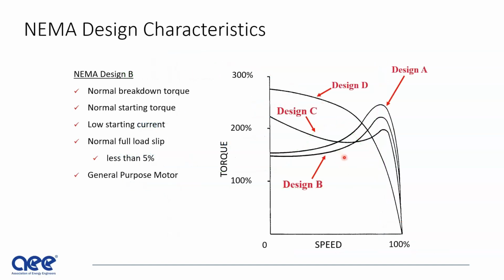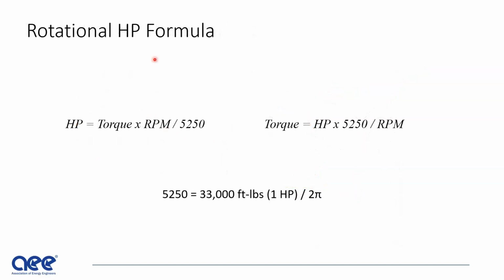Here you see the NEMA design characteristics for different torque curves. They're design A, B, C, and D, and it depends on the application, which is the appropriate design for torque. So how you figure out torque, the horsepower is going to be the torque times the RPM divided by 5250. 5250 comes from 33,000 foot-pounds for a horsepower divided by 2 pi. So the torque is equal to the horsepower times 5250 divided by the RPM.